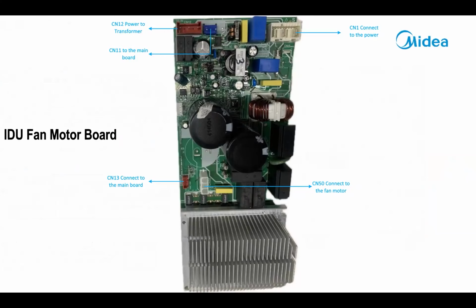CN12 is power out to the transformer. CN11 just goes to the main board. CN50, which is this 3-pin socket right here, is your DC volt. That's your power for your motor. That's power for your fan motor. CN13 next to it is your control voltage for the fan motor, which is set from the main board.